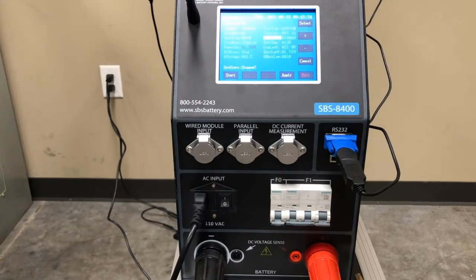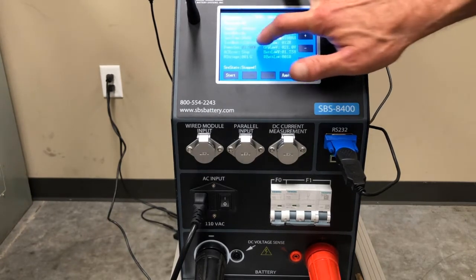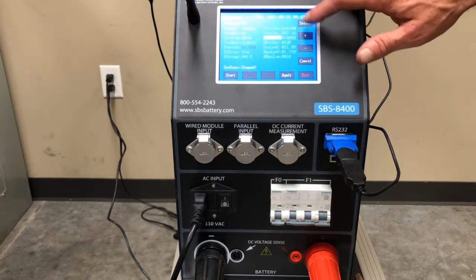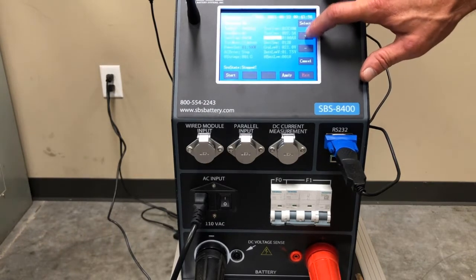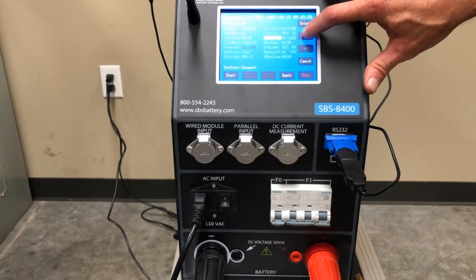Test capacity. How many amp hours do I want to allow to come out of this battery before the test self-terminates? I typically set this at 125% or 130%. Valve regulated, I'll set at 125%. Flooded cells, I'll set it for 130%. So my test capacity, 97 amp hours. I'm going to dial that test capacity up to 125.